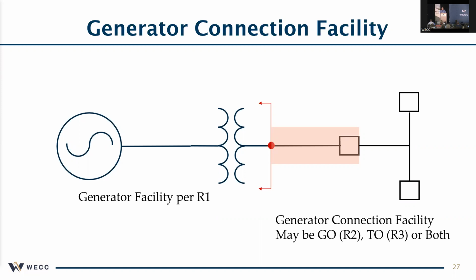The tricky part, the one that's causing the most issue, is this configuration right here, where the generator owner technically owns that line going from the generator up to the bus. Maybe they own the terminal equipment, maybe they don't. But then that bus is owned by the TO, the transmission owner. It's not the GO's equipment, but we're still considering that generating facility's connection facility to go through those breakers, because we believe those breakers can legitimately limit the output of that generator.